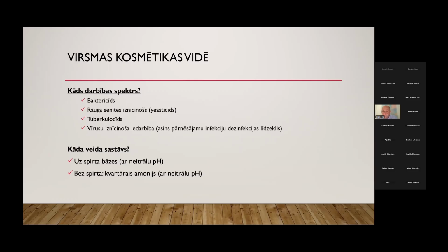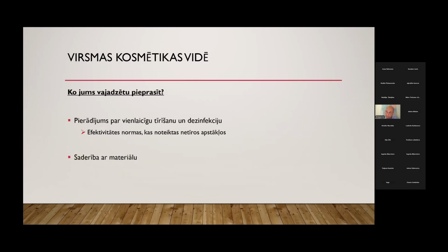And if you make a decision to go for non-alcohol, quaternary ammonia with a neutral pH is also a good solution. But again, ask the same. Make sure that the products you are using are tested in dirty conditions, so they are really cleaning and disinfecting at the same time. And also request a compatibility list of materials.